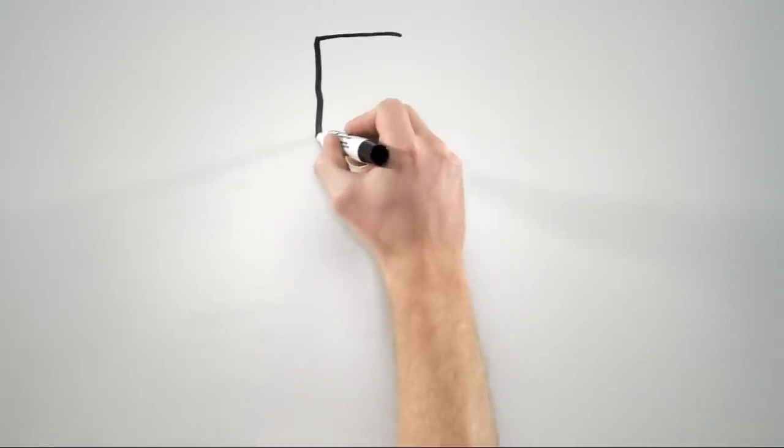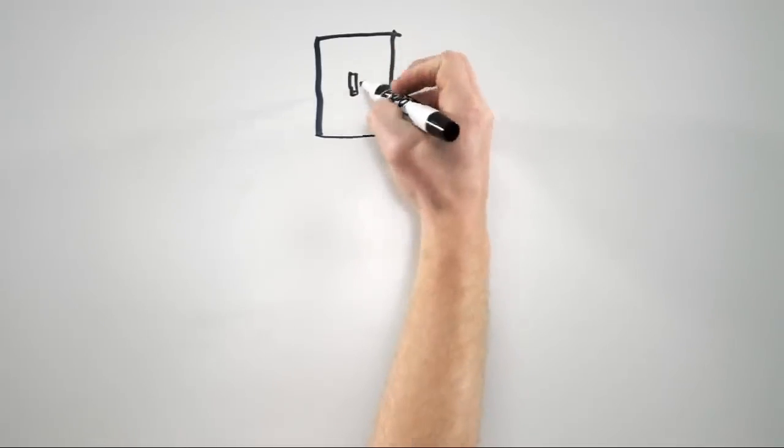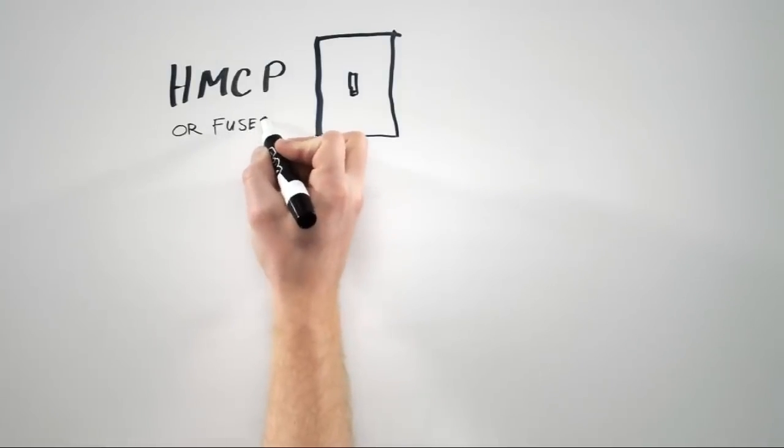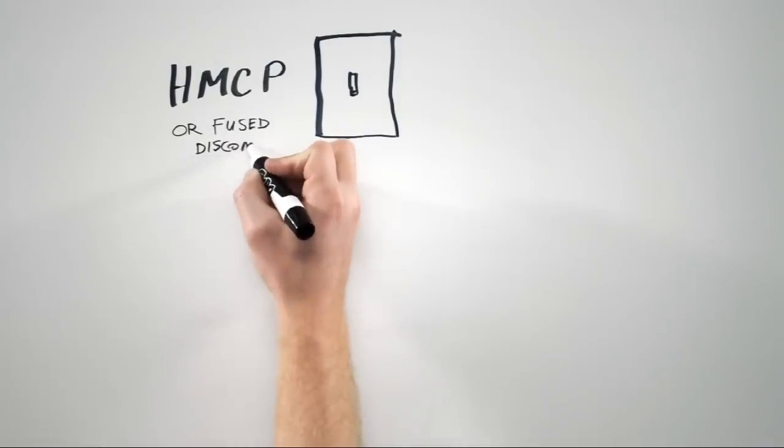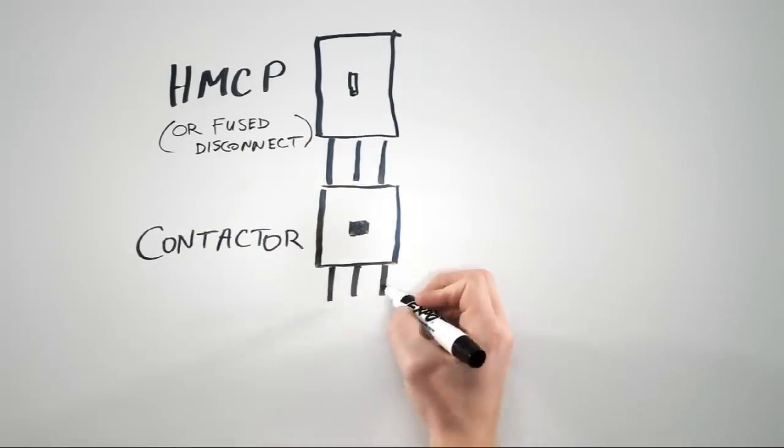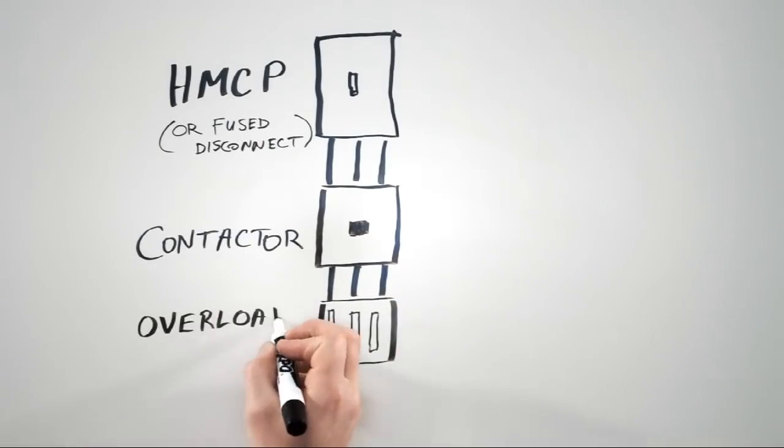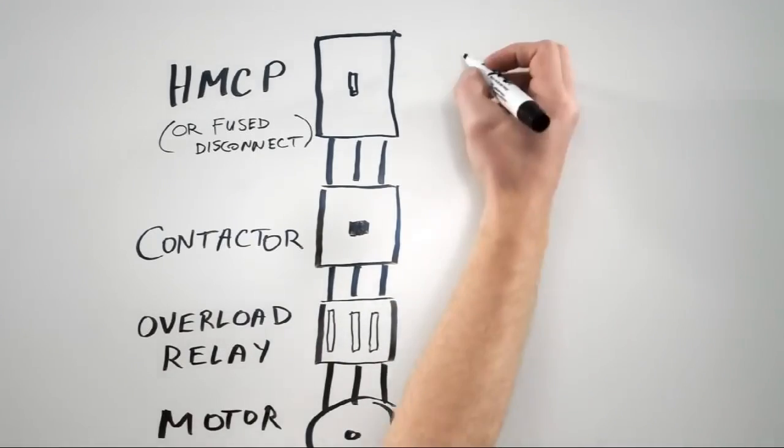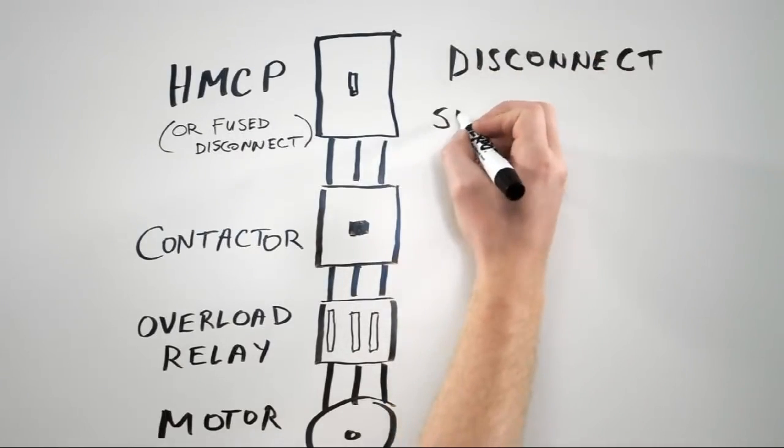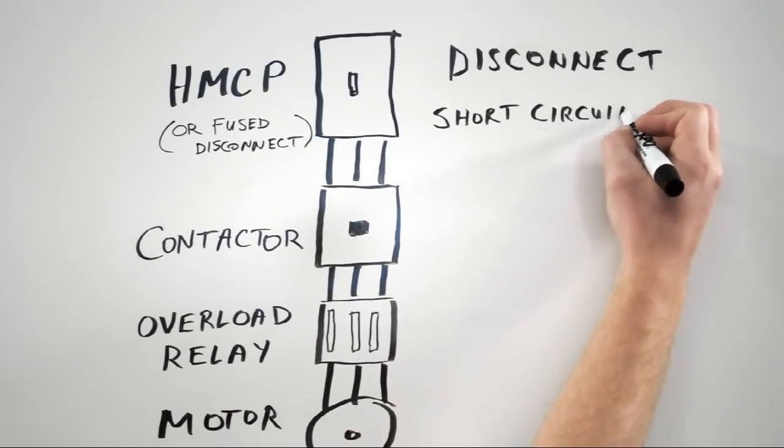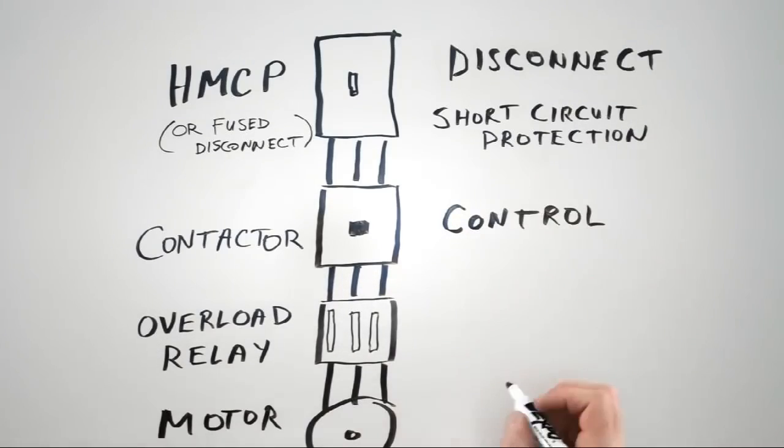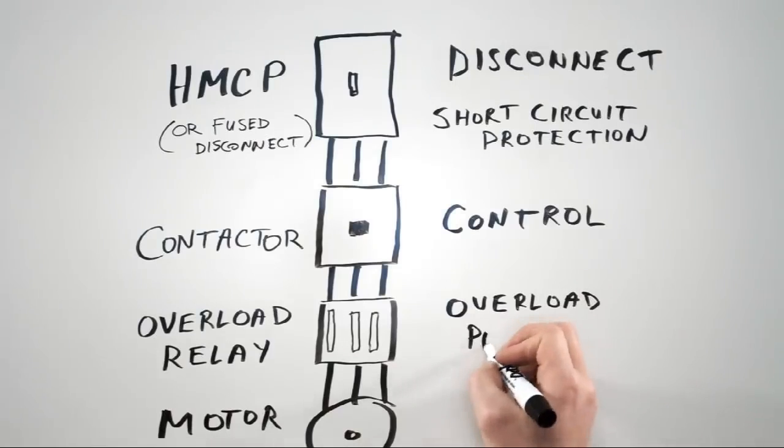Now that we've covered motor protection and motor control, let's put it all together. At the top of the circuit we have our HMCP breaker, or alternately we could use a fused disconnect switch. Next we have the contactor, followed by the Overload Relay. Lastly, we have the cables connecting the Overload Relay to the motor. In this setup, the HMCP provides a way to disconnect the entire circuit from power, as well as providing short circuit protection, since it still has the magnetic protection inside. The contactor provides a means of controlling the motor, and then finally the Overload Relay protects our motor from overload conditions.